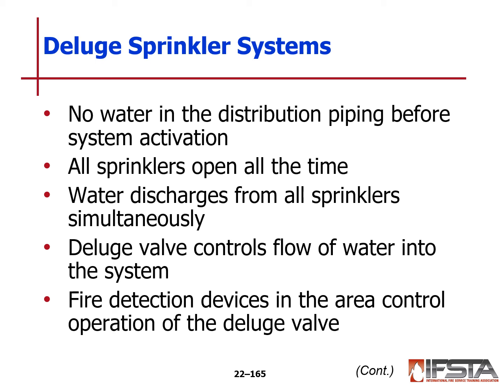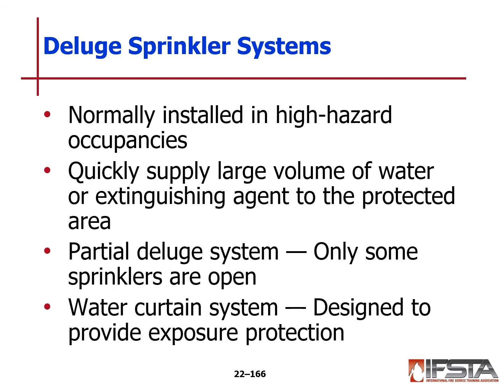The deluge valve controls flow of water into the system. The fire detection devices in the area control the operation of the deluge valve. These are normally installed in high hazard areas or occupancies where a quick supply and large volume of water or extinguishing agent is needed in the protected area. In a partial deluge system, only some of the sprinklers are open. And you may also have a water curtain system, which is designed to provide exposure protection as well.